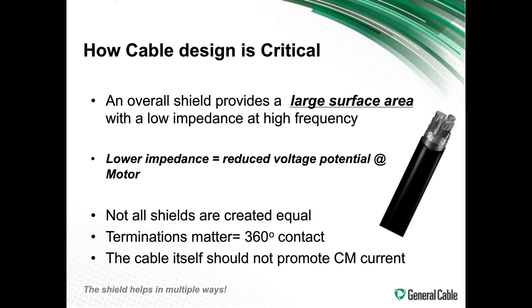An overall shield provides a large surface area with low impedance at high frequency. And that's key because you are working with high frequency when you're working with a VFD. So you need a large surface area. That's what a lot of cables do not afford. If you don't provide that, you're not going to get what you want out of this. So to create that lower impedance path and to reduce the voltage potential at the motor, you need to have a very good large surface area shield.